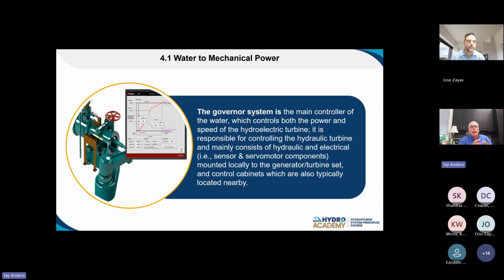That's what we talk about with a governor. When you're offline, not tied to the grid, a governor is strictly speed control. You don't want your unit overspeeding while you're getting it ready to load to the system. But once you're online, all you're doing is varying how much megawatt load, how much work you're going to put into it. So a governor is a load control, a kilowatt controlling device. In a bit we'll talk about excitation, which deals more with reactive, imaginary power. But this is the real power, the real work a hydro unit puts out. The governor controls the water, which ultimately controls how much work the unit can do, how much real wattage it can take on.